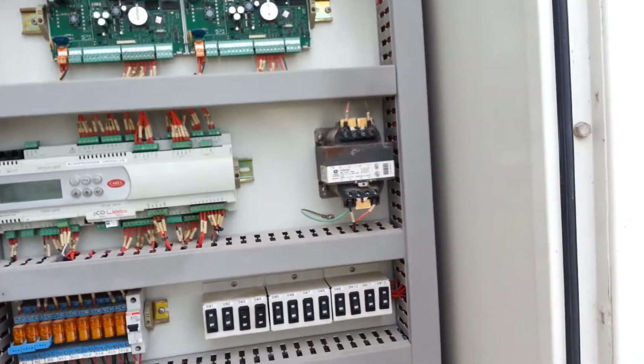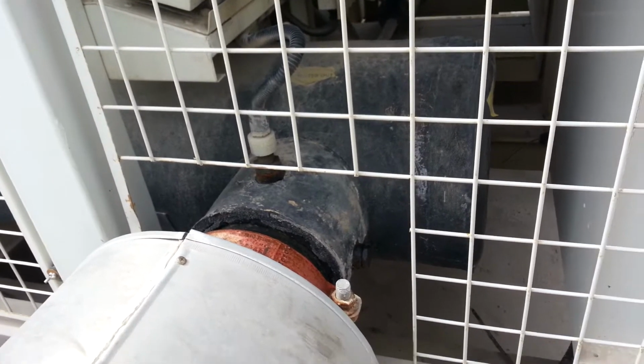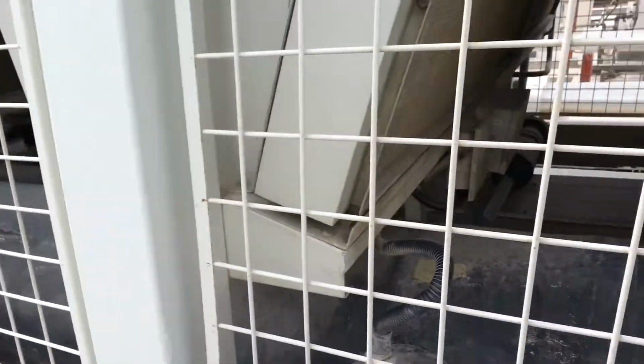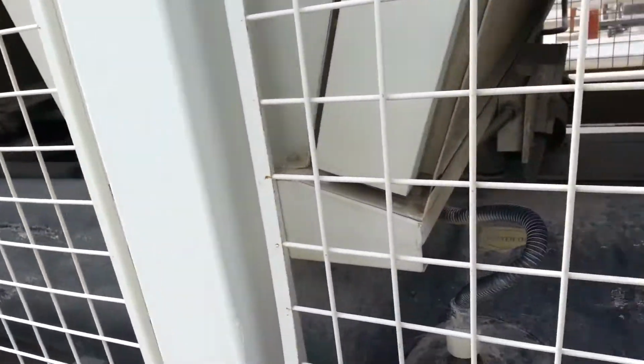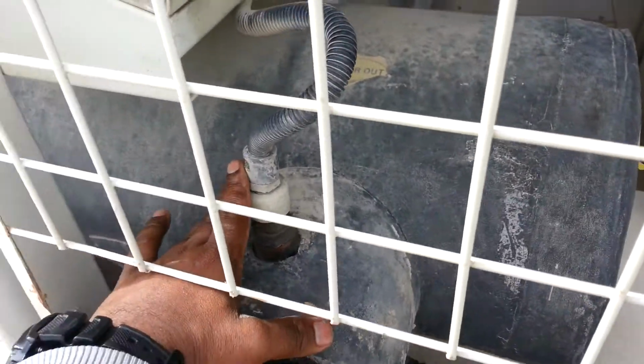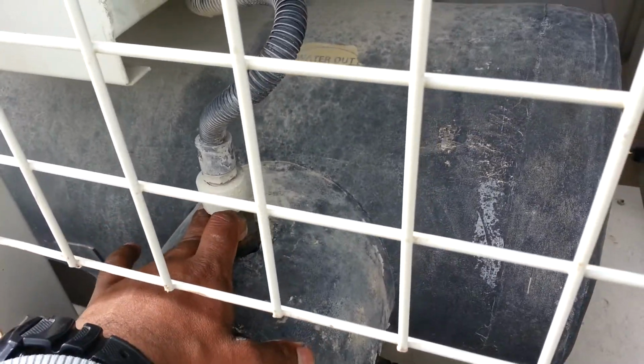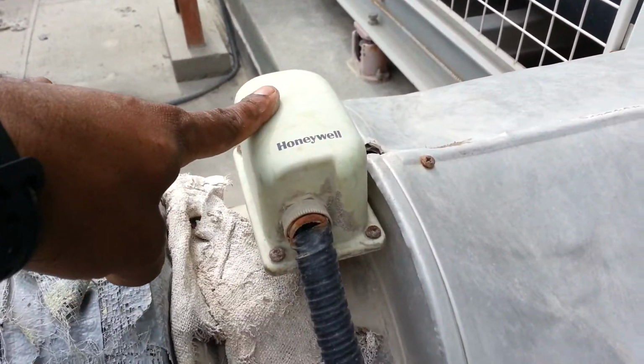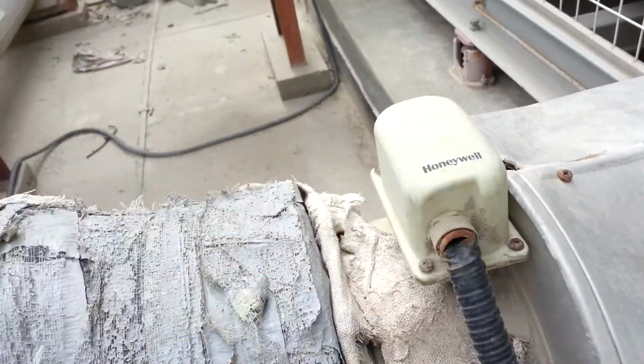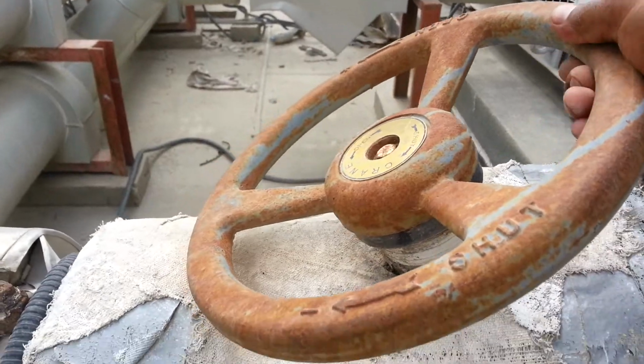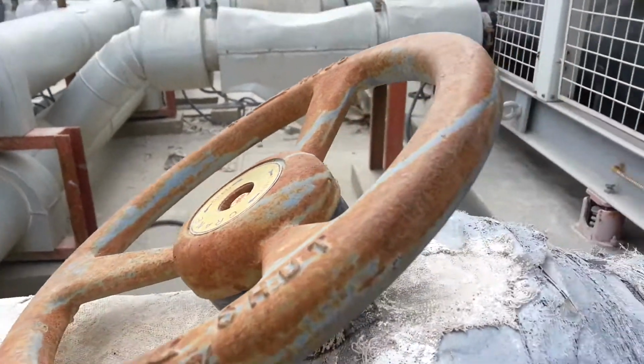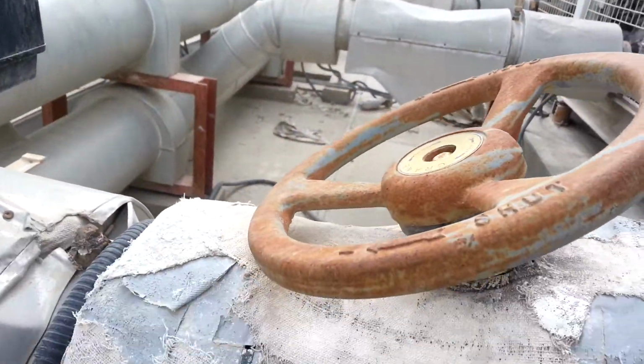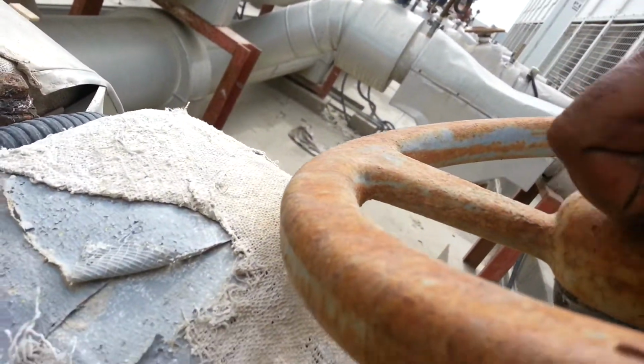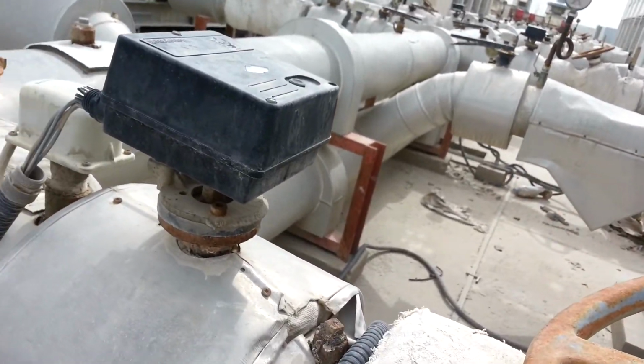Other main parts are, here we can see the cooler or barrel, and here there is a sensor. This is a water out sensor, the chilled water out sensor from the barrel, and this is the one flow switch. This is for DDC, and here there is a balancing valve. This is a flow regulation valve, and it already has readings. We can adjust the percentage of flow through this reading.